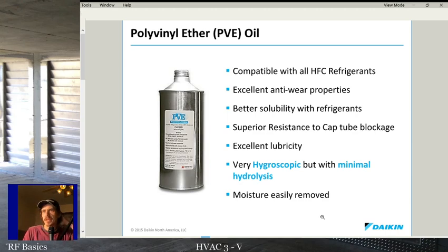With the PVE, I've seen mini splits that had issues where the suction line was basically going into negative pressure, so it was sucking air in through a leak, and it had tons of moisture in the system, and it took like 36 hours of having the vacuum pump hooked up, but it eventually hit 500 microns.